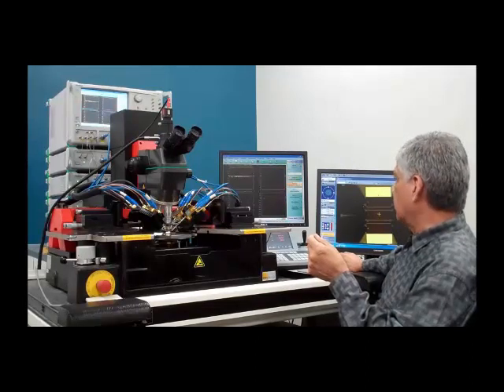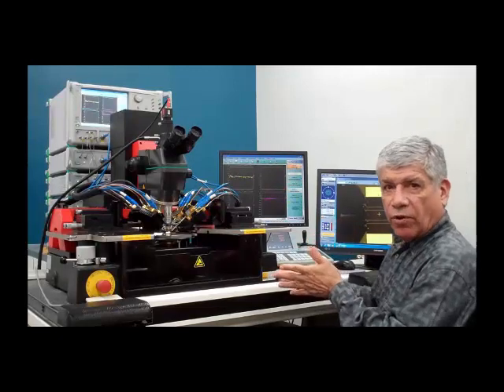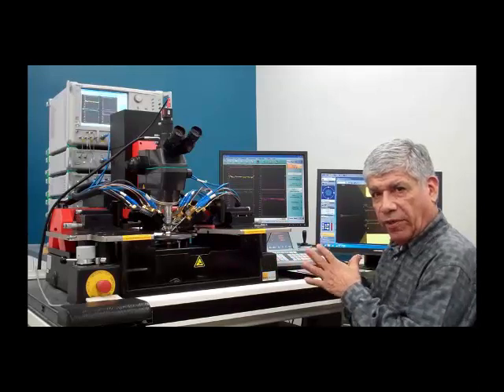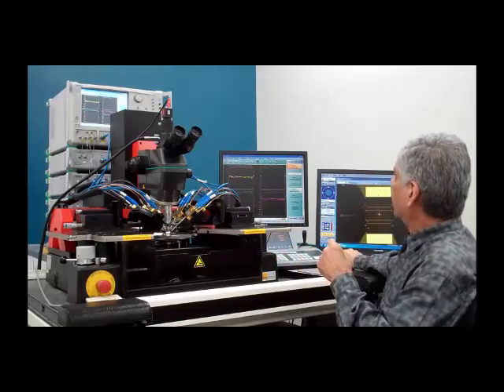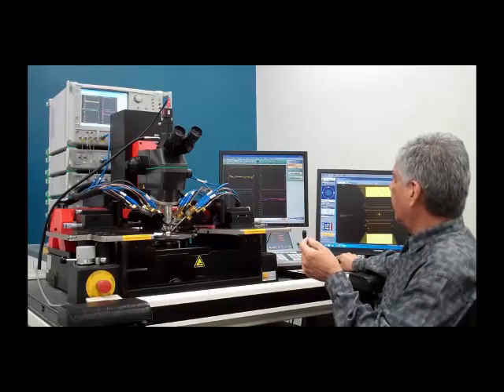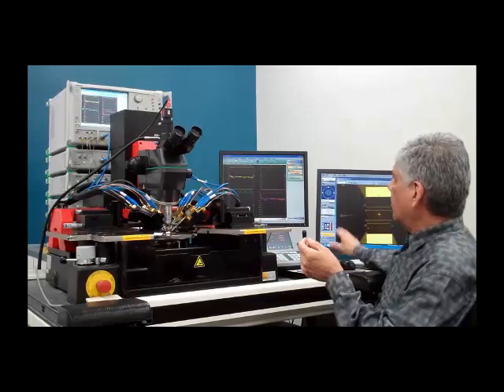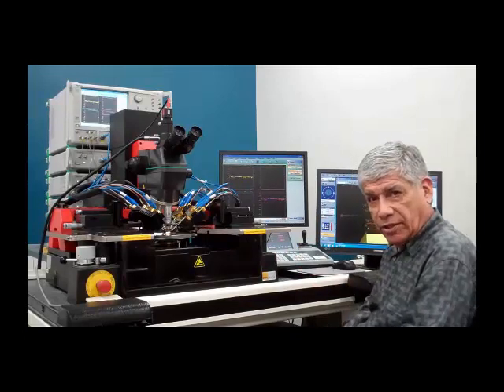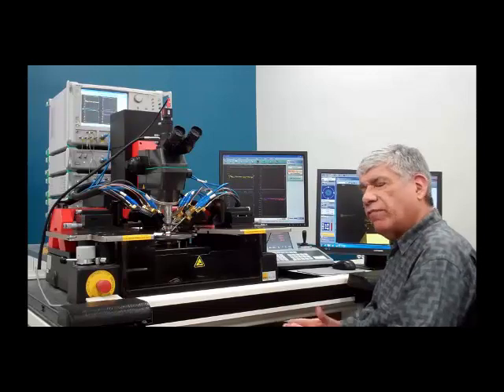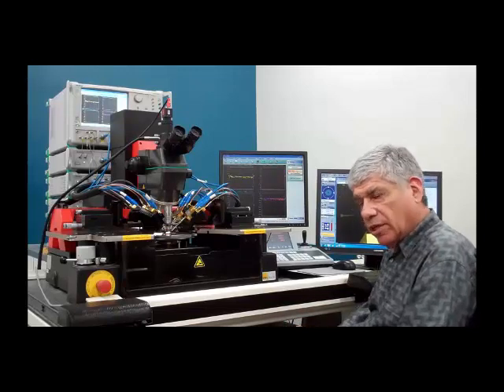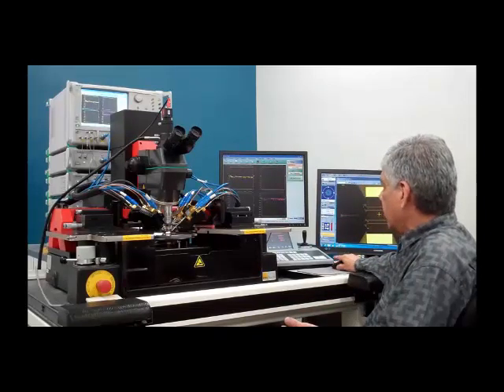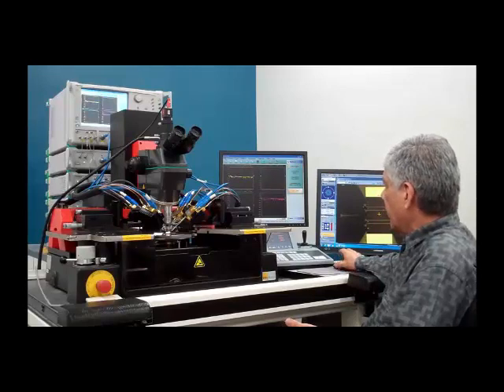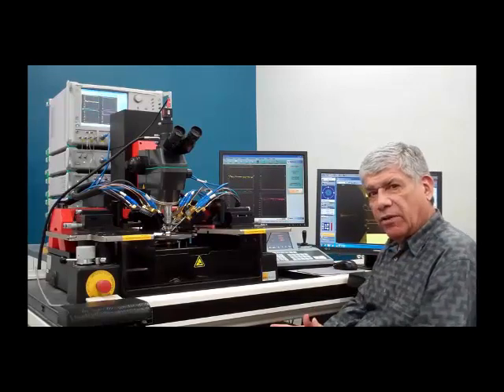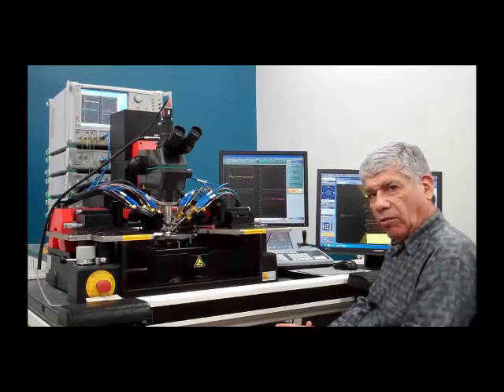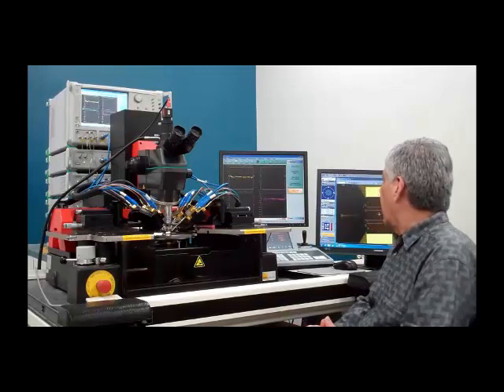And here's the standards setup. But before we do that, we want to confirm that it's set up properly for the calibration that we want to do. So we go to Modify, and here's where we choose the type of calibrations. For on-wafer measurements, broadband measurements, we pretty much always go with LRM. It's a very quick and easy way to get very accurate on-wafer calibrations.